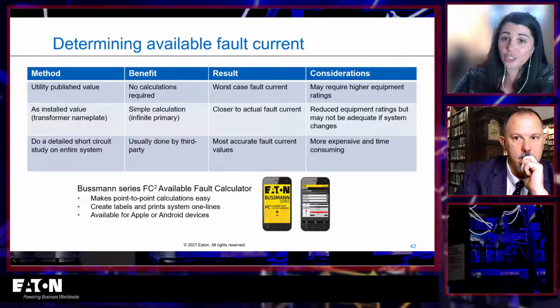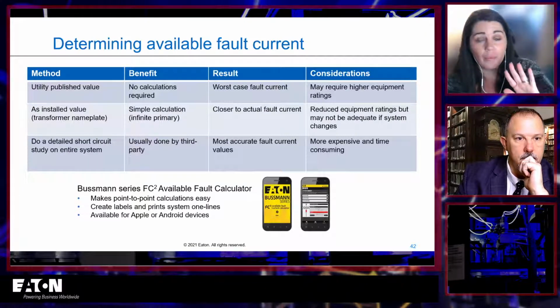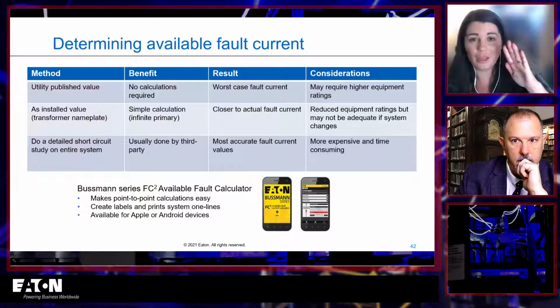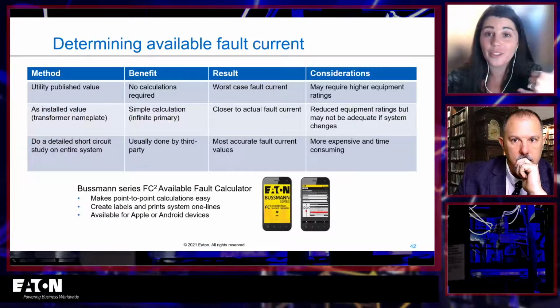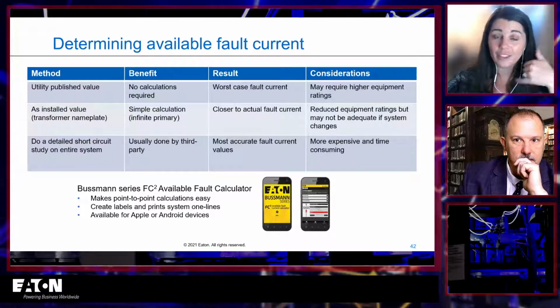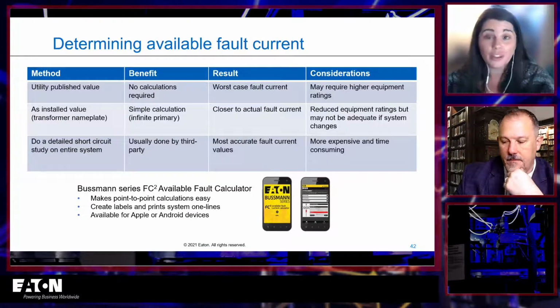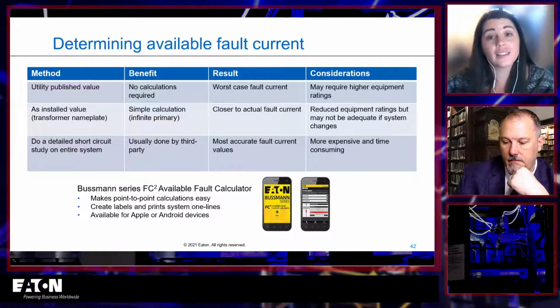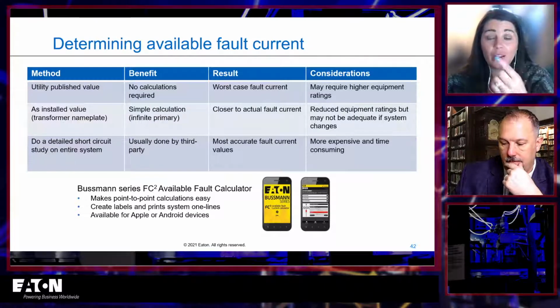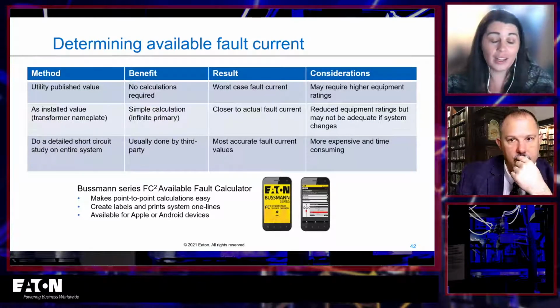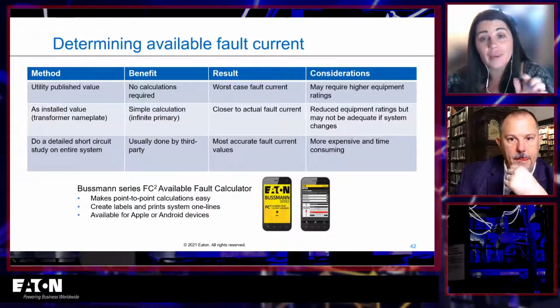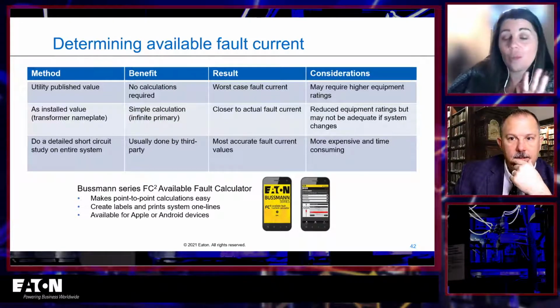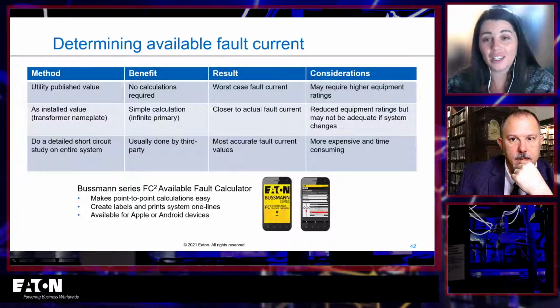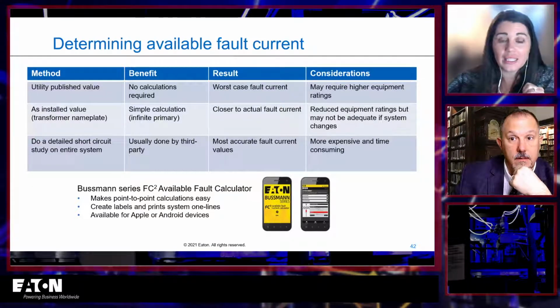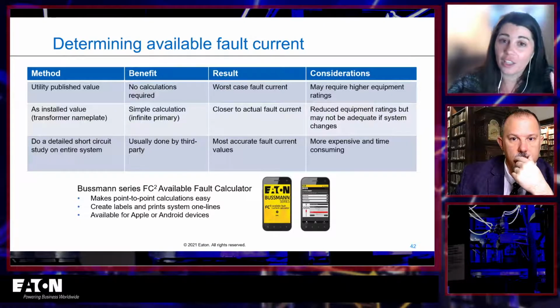To determine the available fault current, there's a couple of ways. The easiest thing to do, maybe, depending on your utility, is to call up your utility and ask them what the available fault current is at this location. They should be able to tell you what it is. When I talked to a lot of electricians and inspectors, they may disagree that this is the easiest method, because getting a hold of the right person at the utility company and getting them to call you back is not always the simplest, but you don't have to do any sort of calculation.